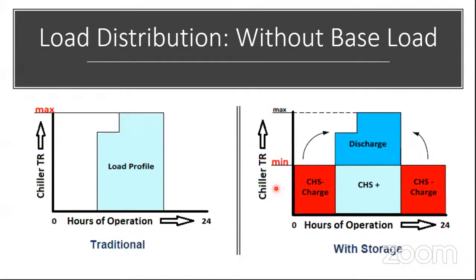Now, how do we distribute the load? Load distribution without base load. We will see why this base load comes into picture. It is for this kind of load profile where the hours of operation is only during the day, from here to here. At night, there is no load. For such cases, your brine chiller is operating, it is satisfying the load, and whatever extra load is there during the daytime is being taken care of by thermal storage, like this. And here, your brine chiller is charging the thermal storage tank. So this is how it would be when there is no base load.